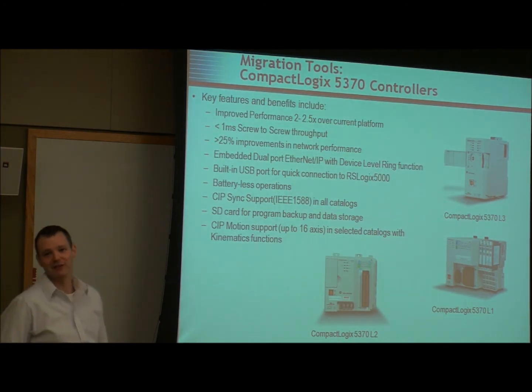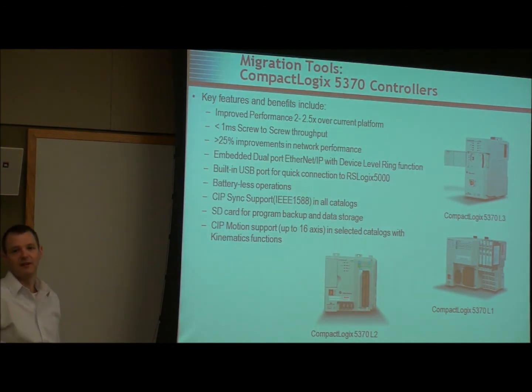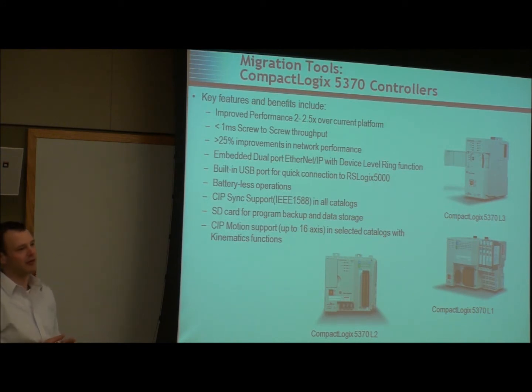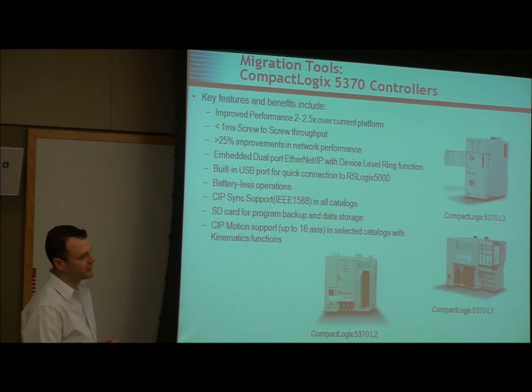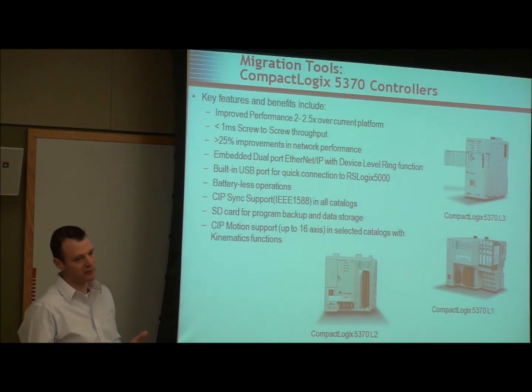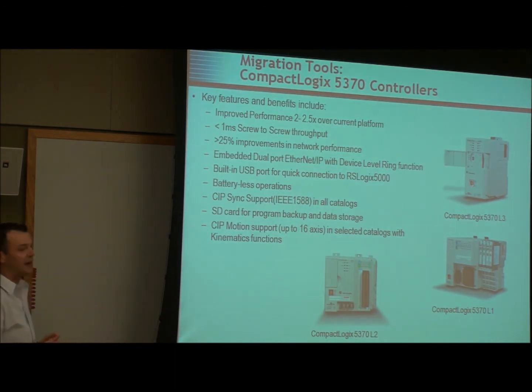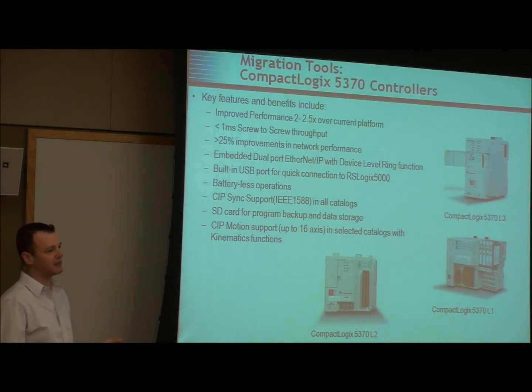The USB port is a nice feature — you can actually connect to it without having to have an Ethernet connection. Rockwell does make a supported serial converter for laptops without a serial port. There are third-party ones on the market, but they're not supported by Rockwell, so tech support won't be able to help you with those. The new CompactLogix processors also don't have batteries — they have a capacitor that serves the same function, so you don't have to worry about the battery going bad.